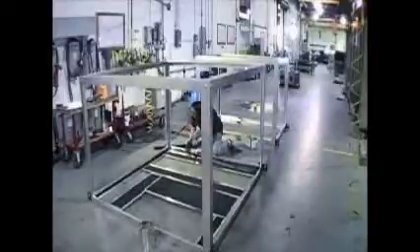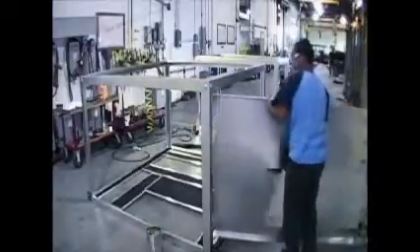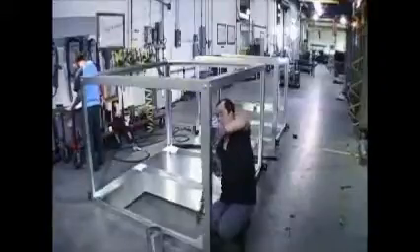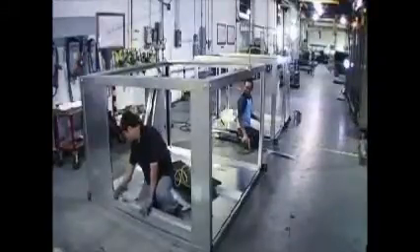Let's go through the unit the way a consulting engineer would look at it. I really think that the casing should be made with a double wall with insulation between it. Anything downstream of the cooling coil where condensation is likely to occur shouldn't have materials that absorb moisture. You come from the outside into the unit through some storm-proof louvers so you don't pull in snow and rain.